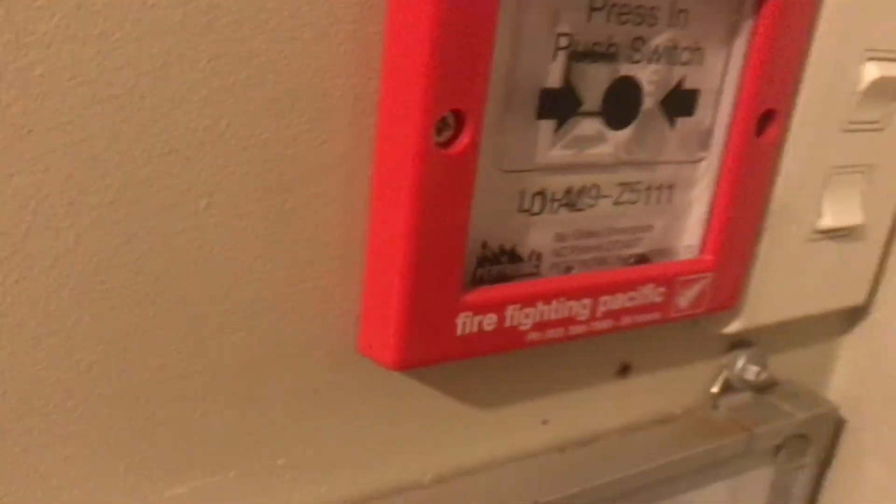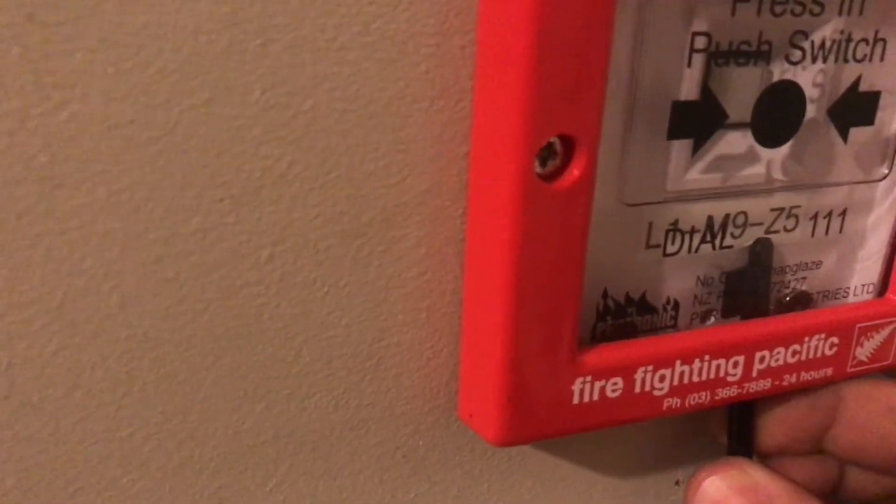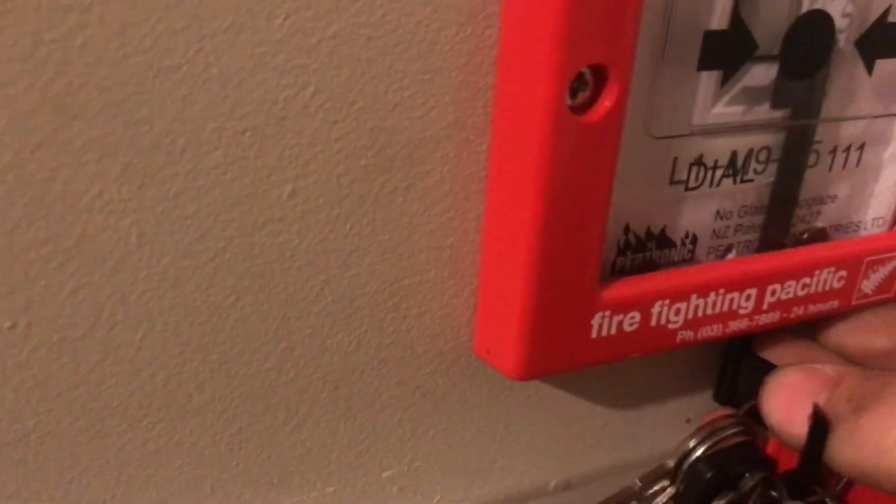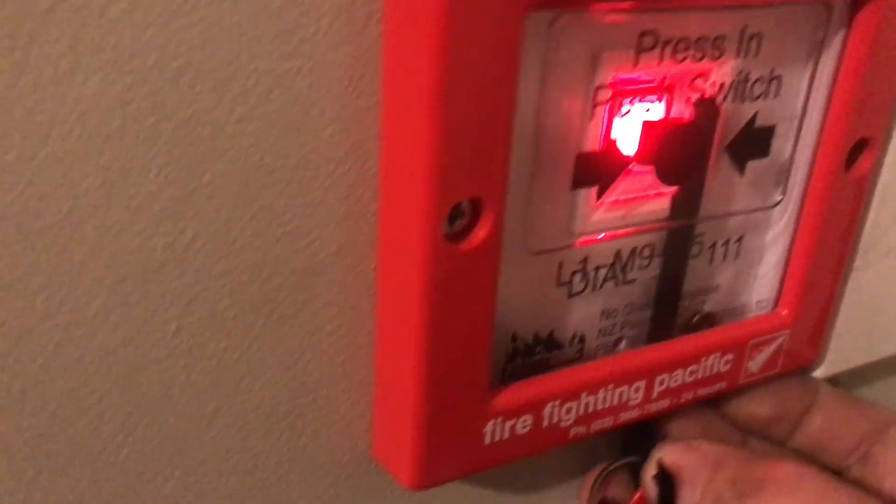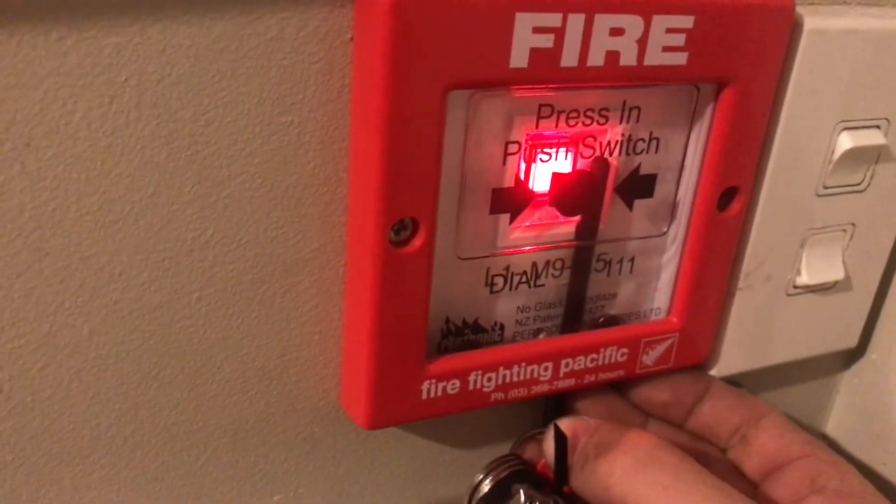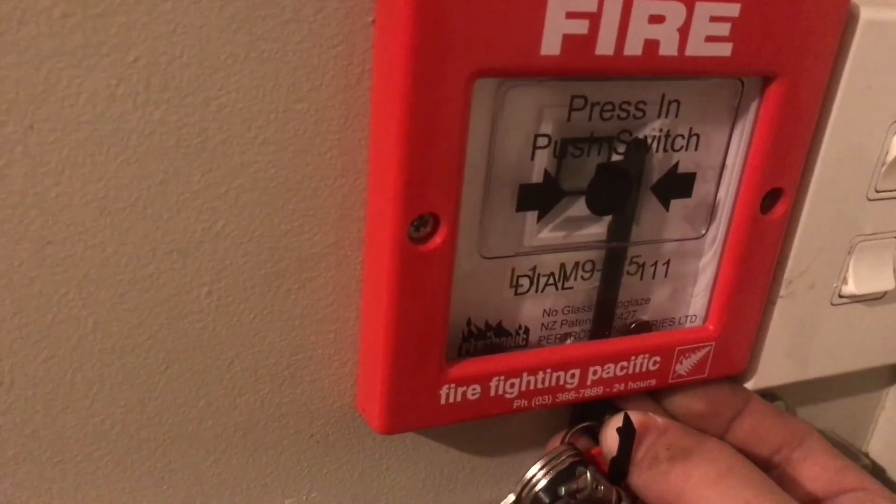And finally we have another conventional call point. This one is Loop 1, Zone 5, Module 9. Bit hard to get the key in this one. And it has alarm verification as well.